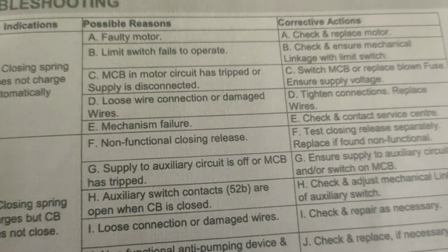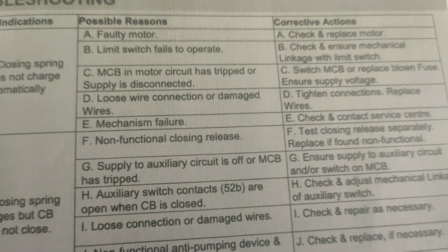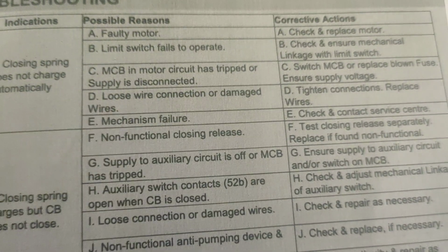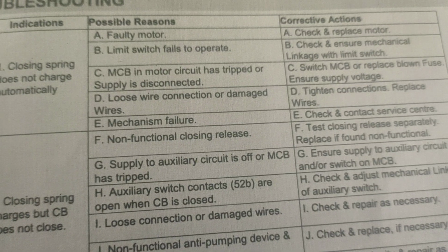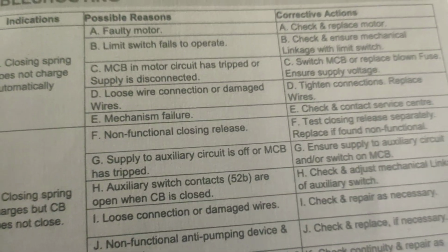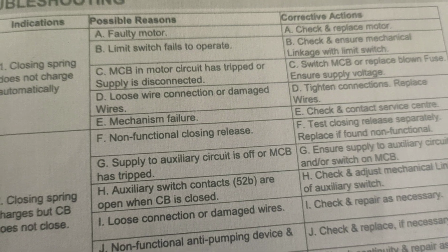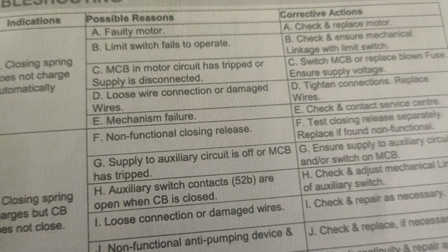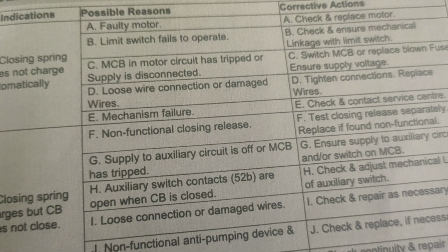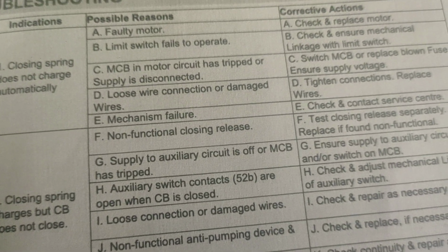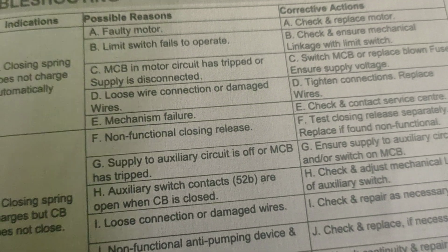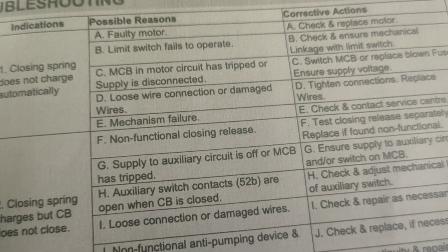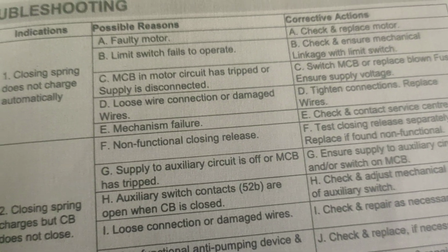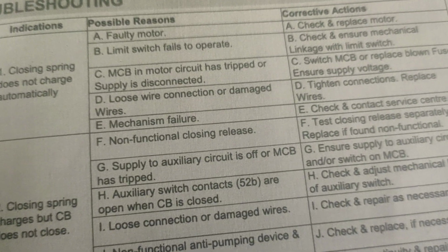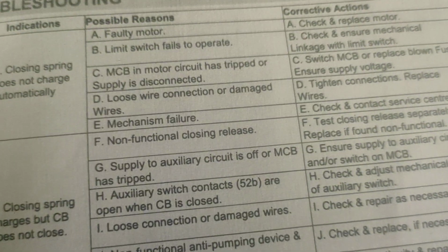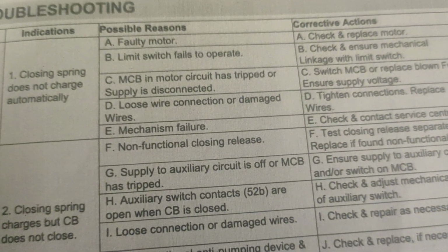The mechanism problem: mechanism failure inside it. The latches, different nuts and bolts, different latches, dashpots and different types of connections are inside the mechanism. If there are different types of problems, wear and tear, you cannot easily solve this mechanism problem, because it can be solved by the OEM engineers. If some parts are damaged and you can replace the parts of the mechanism, the mechanism will be good and the circuit breaker will close again.